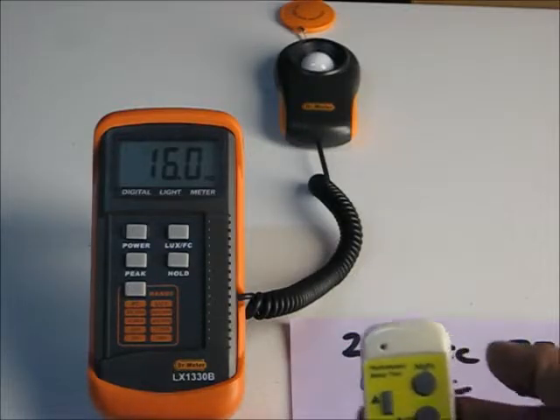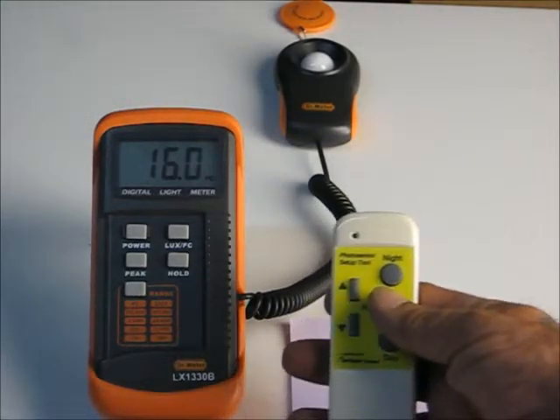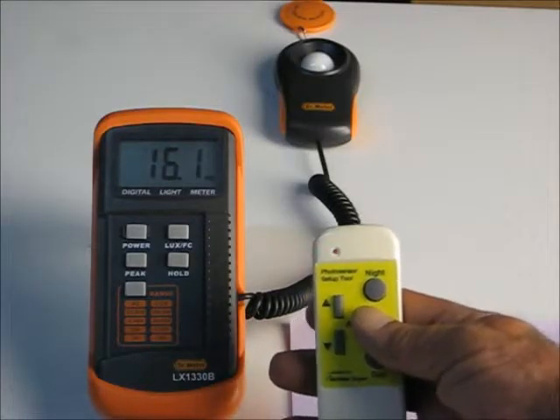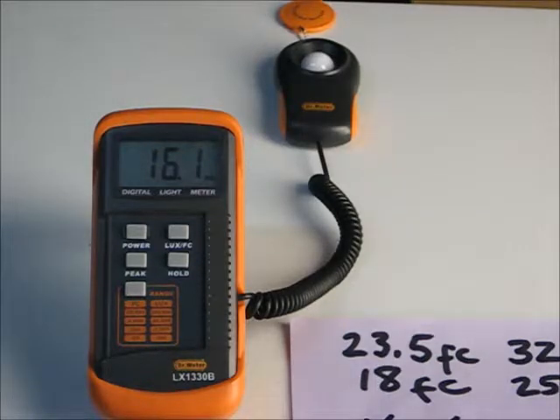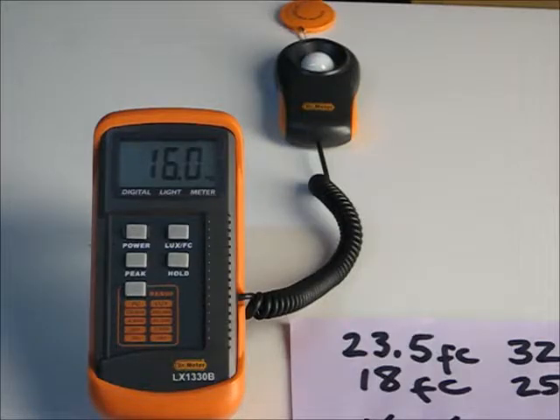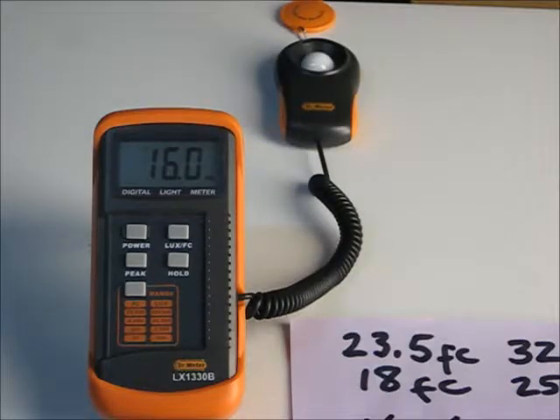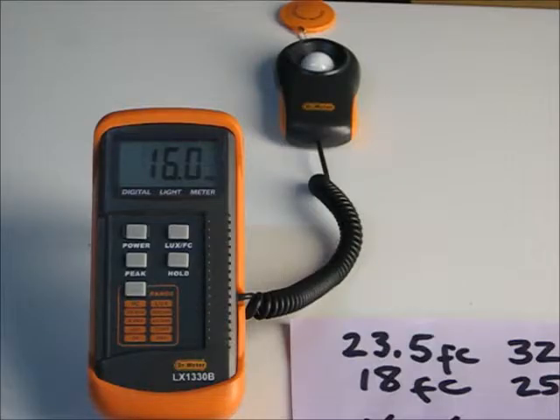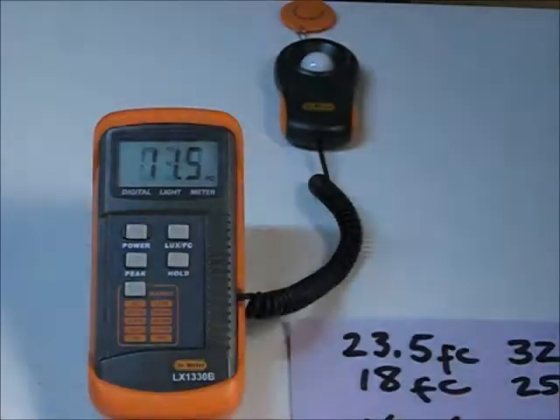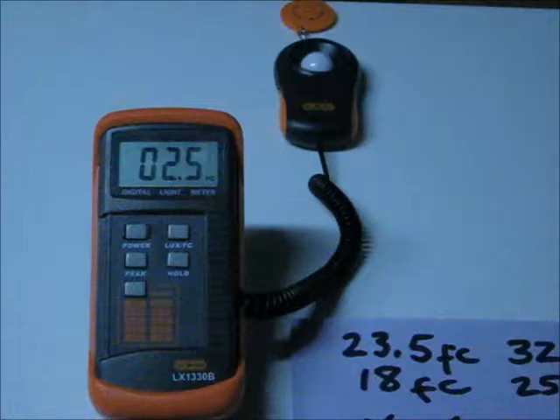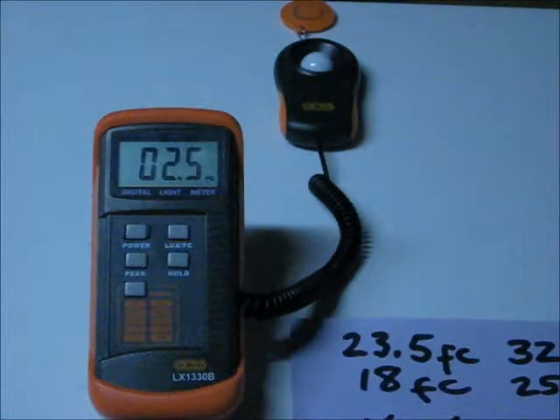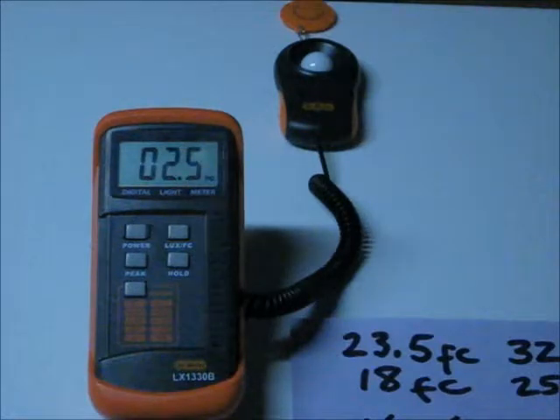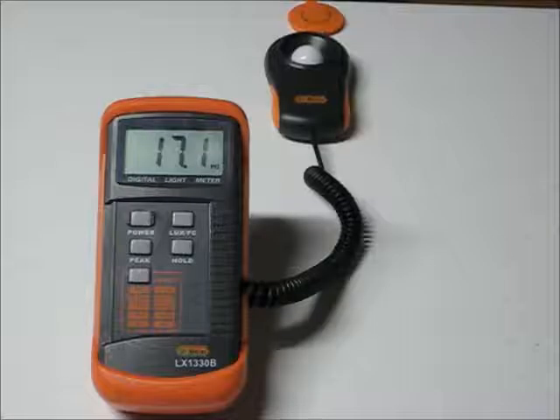Then I'm going to tell it I'm finished with my daytime calibration. Okay. And then I'm going to place it back in auto. And hopefully it will hold there, showing us that we've got a good calibration. Okay. I don't see it moving. So we're at about 16, which the 25-watters ought to be able to reach when we put them back in. So what I'm going to do is kill our artificial daylight, and we should see the sensor come back up to 16 or so. This may take a while, so I'll get back with you.